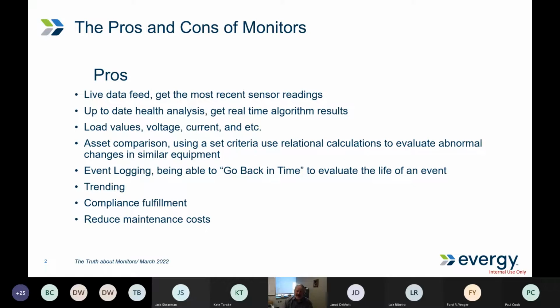Event logging allows you to go back in time. We use event logging here at Evergy all the time. When an event or a fault occurs, we gather data from the substation, the relay, and the DFR, and pack it all together so we can break that event down back in time, millisecond after millisecond. And then there's trending, which we also have to do.